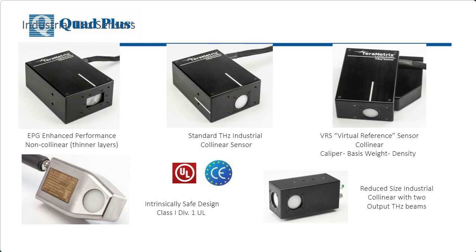We have also, in certain circumstances, been able to implement that online as well, using two sensors or a sensor and a reflection plate. We can sometimes do a calibration of that on the fly. So there's a lot of opportunities with a terahertz sensor that we didn't get into today, but those are the typical ways that we make sure that the calibration is correct.